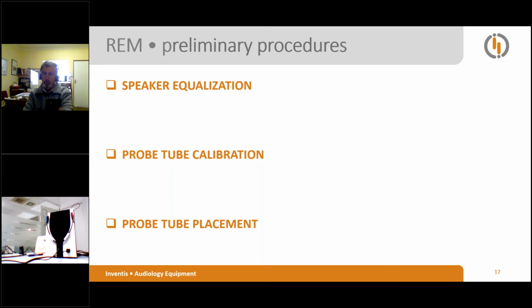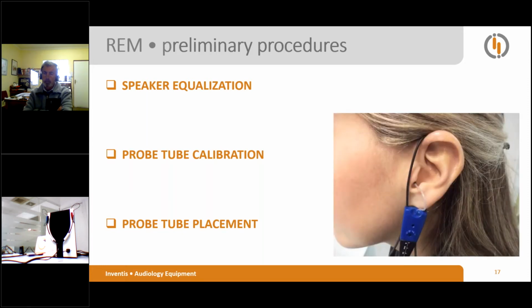Important to underline that the probe tube must be calibrated every time they are changed. It is very important. Every time the test is conducted on a new patient, the system will prompt the user to run the calibration of the tubes before the first measurement is made.